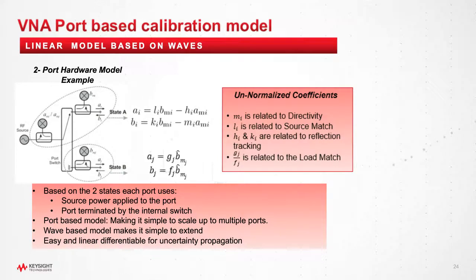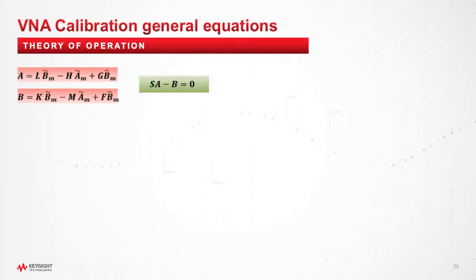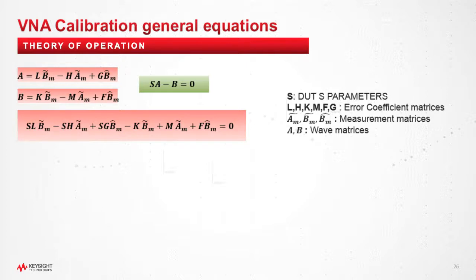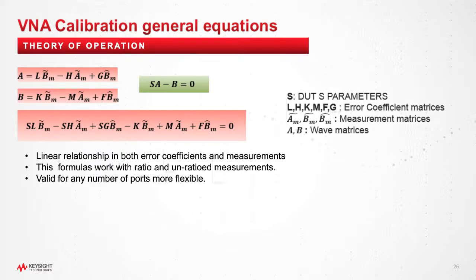So if you generalize these things into matrix form, then you can write an equation which links the error coefficients, H, K, L, M, in the form of matrices, the measurement matrices, and the wave matrices, A and B, which of course, if you look at the S parameter traditional equation, will link the S parameter of your unknown device. These relationships are linear both in the error coefficients and in the measurement. So you can use that for the calibration if you know S, or for the measurements if you know the error coefficients matrices, H, K, L, M, F, G. It's valid for any number of ports, it's very flexible, and is always defined because the S parameters are always defined. So you can use it for a short, for a load, for an open, everywhere.